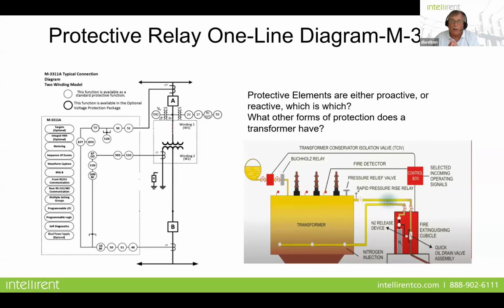But I always categorize the protective relays in two separate sections: those that are proactive and those that are reactive. The reason I make this distinction is that if a differential relay protecting the transformer trips, that means you've already got a problem in the transformer itself, because the current should equal what's going in and coming out. When there's a fault internal to the transformer, that's where the current is going to flow, and you'll get this difference in current. The other, which are proactive, are those elements that actually save the transformer from external conditions, things like volts per hertz that we'll talk about in just a little bit, something going on outside the transformer that could actually damage it. Those are proactive elements.